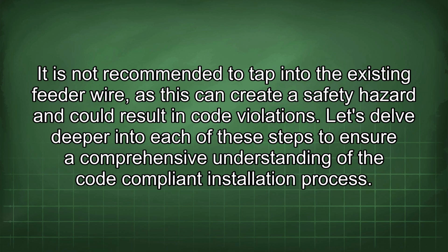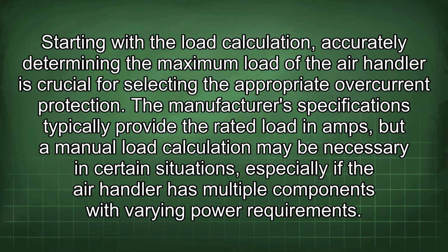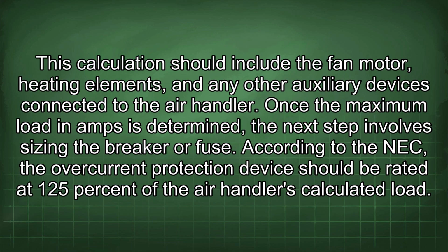Let's delve deeper into each of these steps to ensure a comprehensive understanding of the code-compliant installation process. Starting with the load calculation, accurately determining the maximum load of the air handler is crucial for selecting the appropriate overcurrent protection. The manufacturer's specifications typically provide the rated load in amps, but a manual load calculation may be necessary in certain situations, especially if the air handler has multiple components with varying power requirements. This calculation should include the fan motor, heating elements, and any other auxiliary devices connected to the air handler.